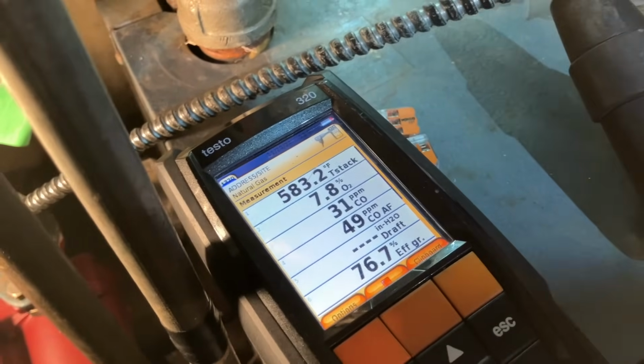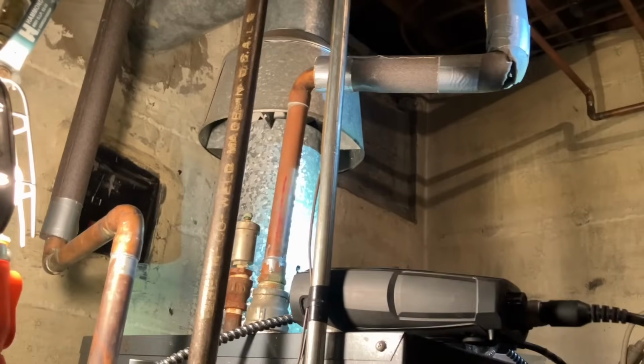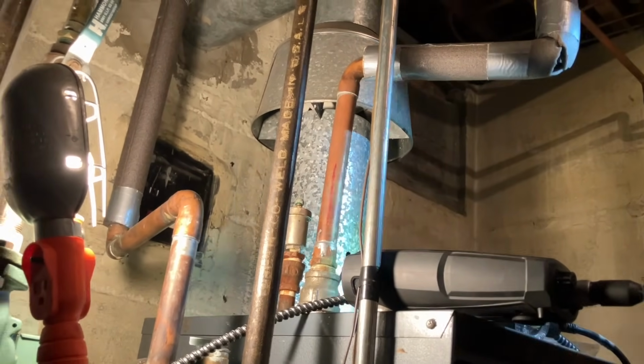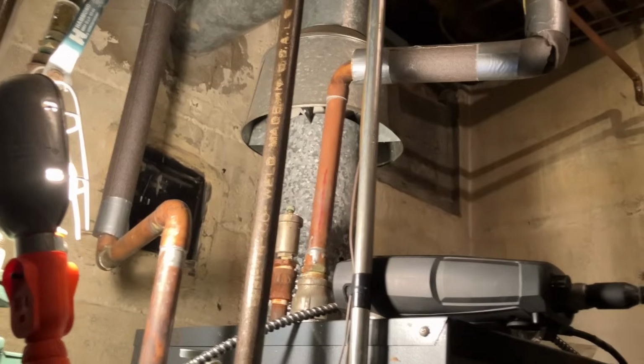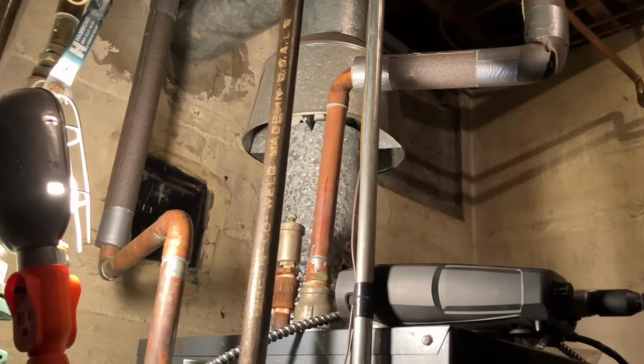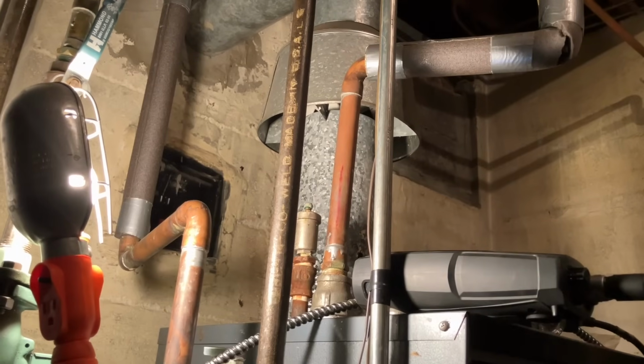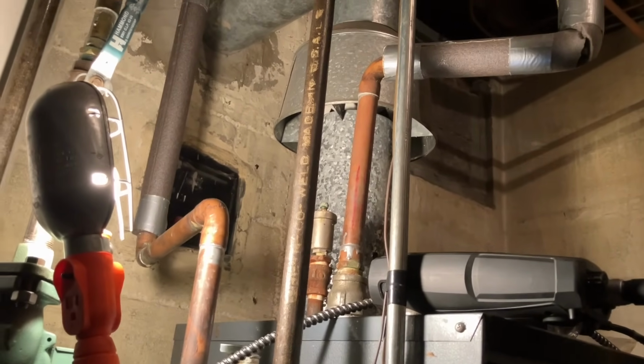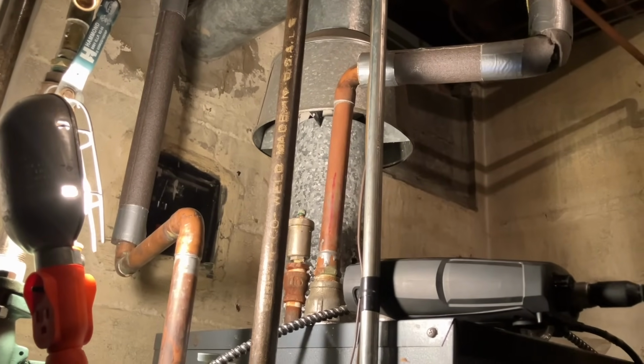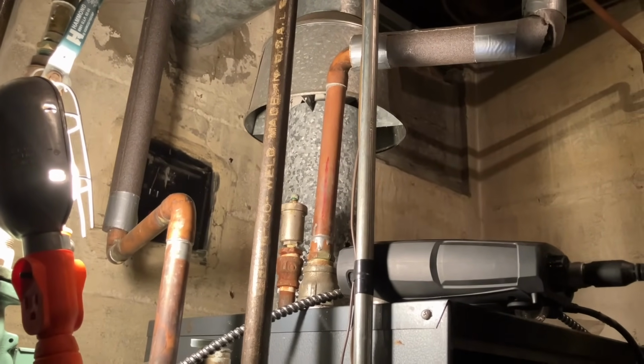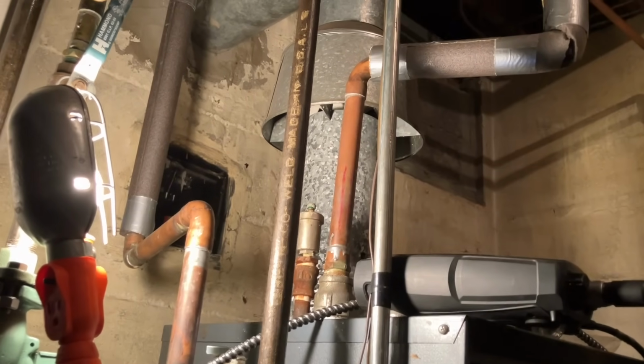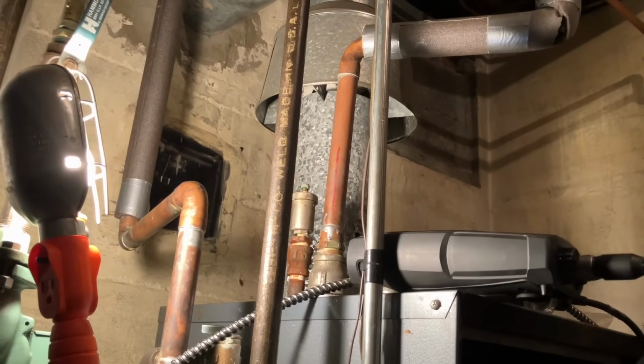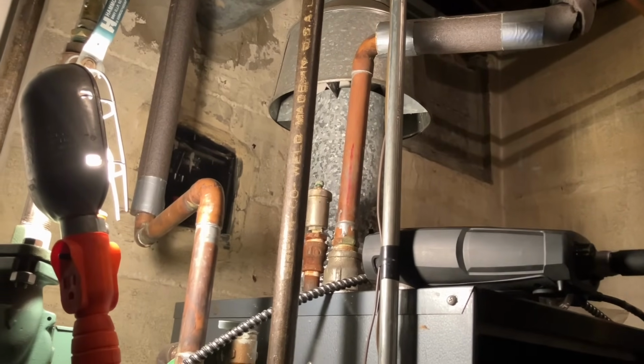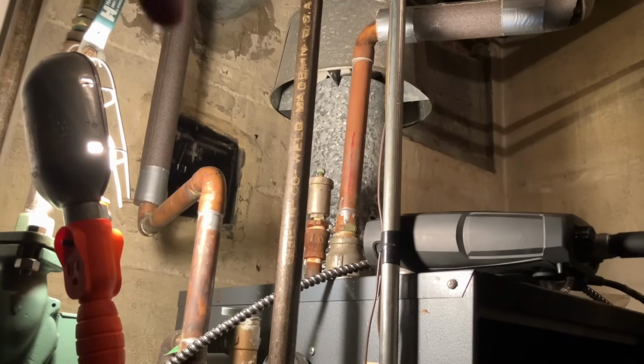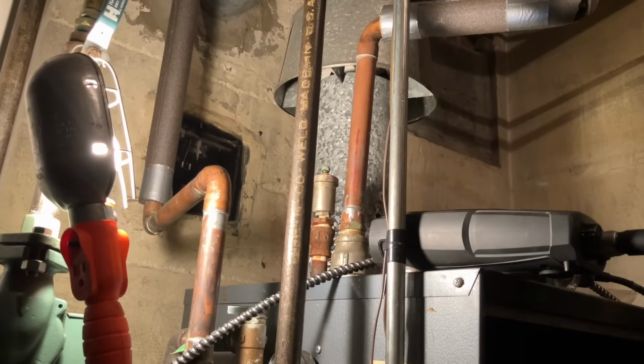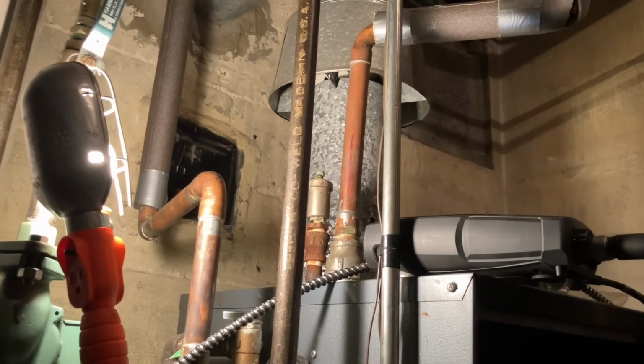And that's the reason why, with gas-fired equipment, we need to install a UL-listed stainless steel chimney liner when we convert a home from oil to gas, because in our area the chimneys are lined with terracotta. The exhaust temperature of an oil boiler will not condense by the time it gets to the top of the chimney. On a gas-fired boiler, which is significantly lower, we line the chimney, because condensation will form. It's a low temperature to start with, and by the time it gets out of the chimney, some of it has turned into condensate already, and that's very acidic. It eats away the terracotta lining.